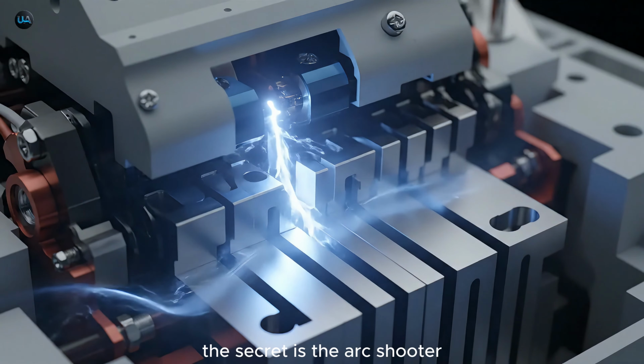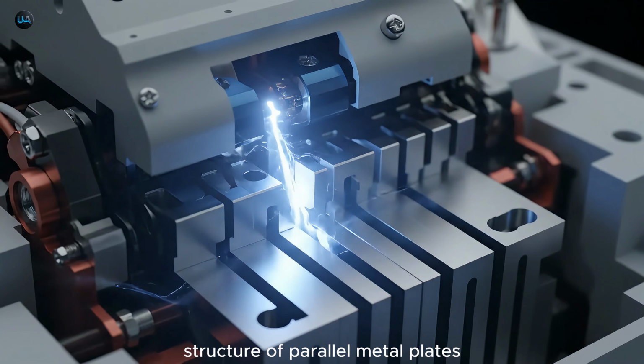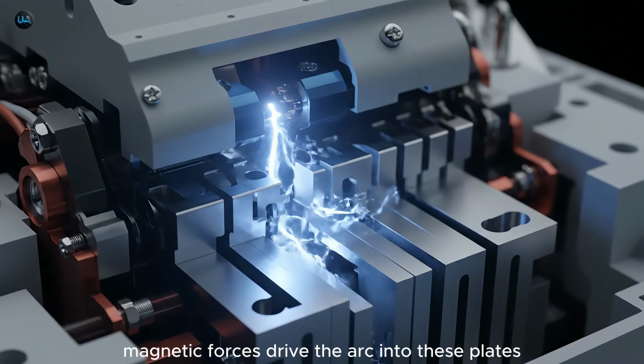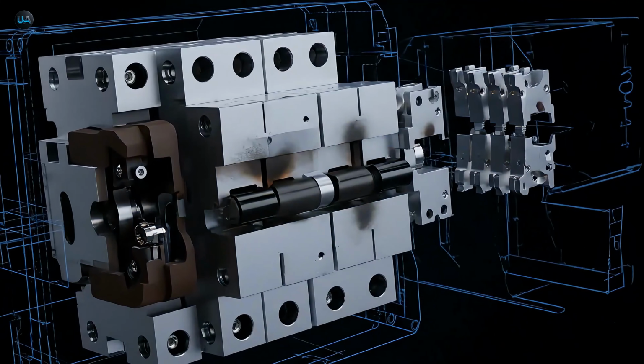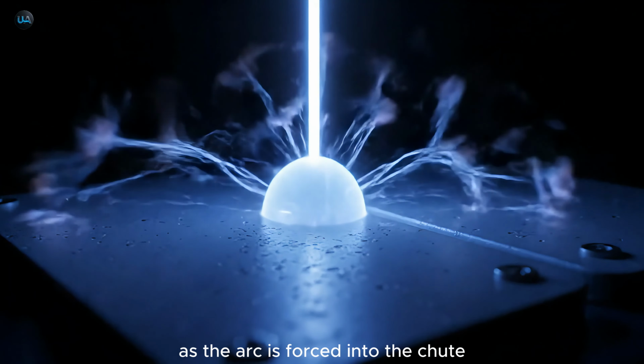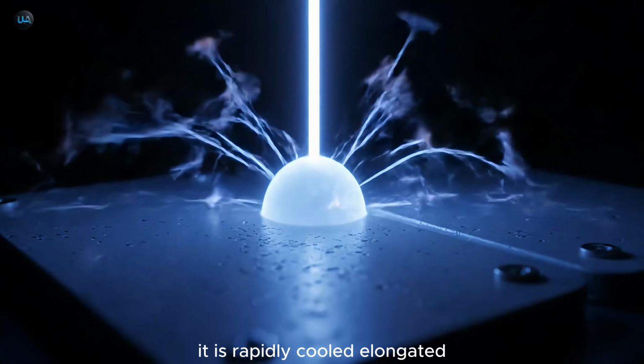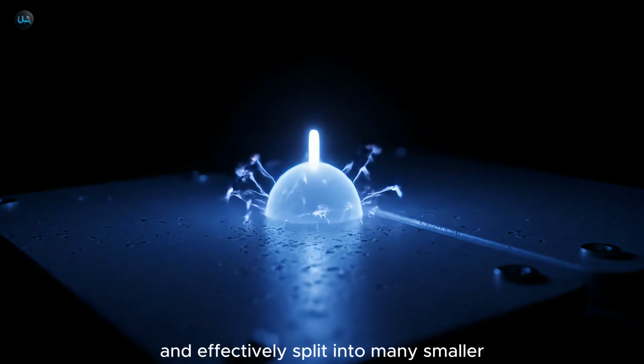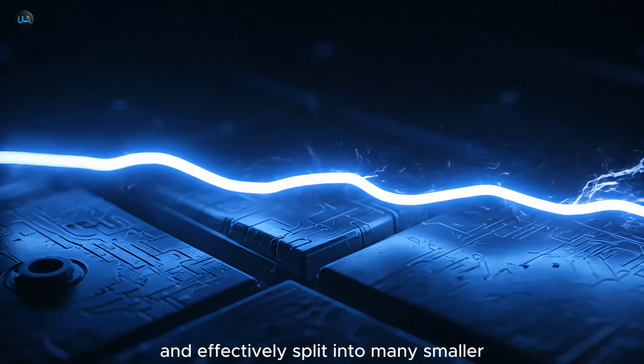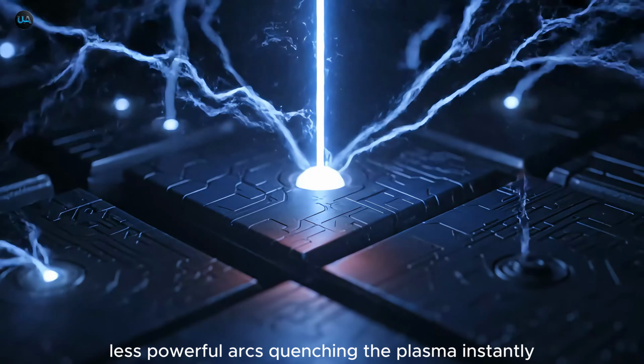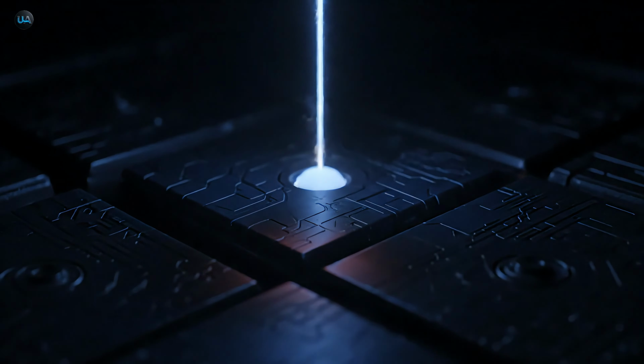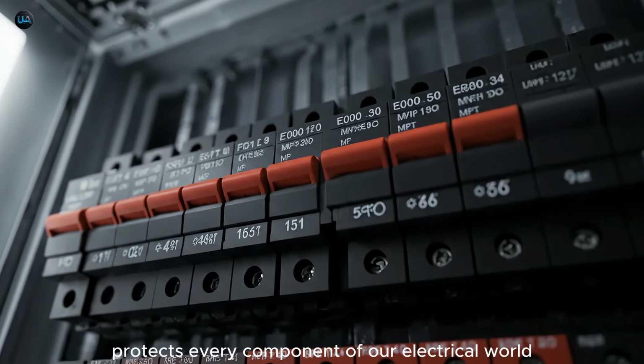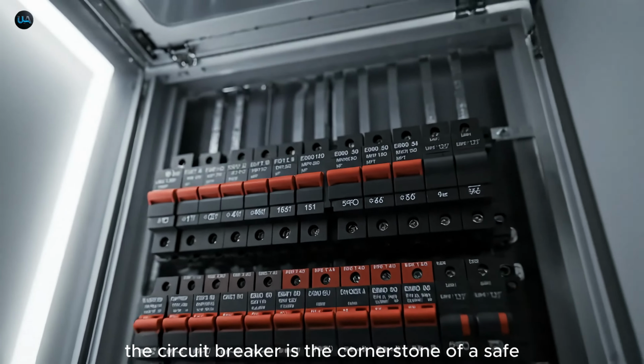The secret is the arc chute structure of parallel metal plates. Magnetic forces drive the arc into these plates. As the arc is forced into the chute, it is rapidly cooled, elongated, and effectively split into many smaller, less powerful arcs, quenching the plasma instantly. This brilliant design protects every component of our electrical world. The circuit breaker is the cornerstone of a safe, modern power grid.